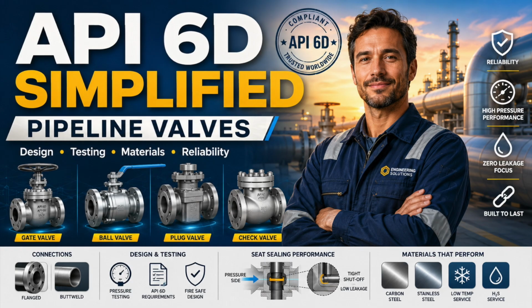Installation can create the final failure. Do not use flange bolts to pull misaligned piping into position. Do not force a heavy valve into a stressed line. Do not ignore actuator support. Do not expose soft seats to uncontrolled welding heat. Do not allow debris into the body. Do not treat the valve as a structural correction device for poor construction.